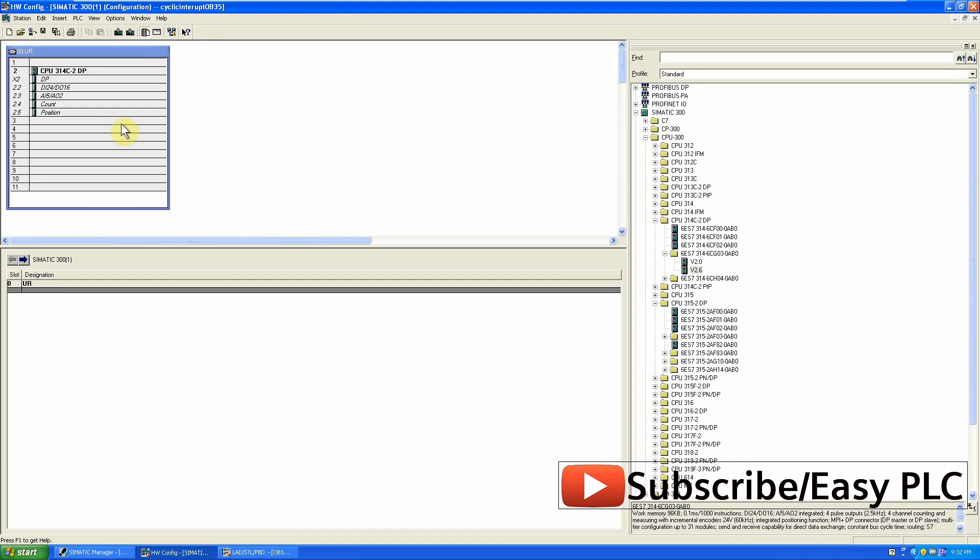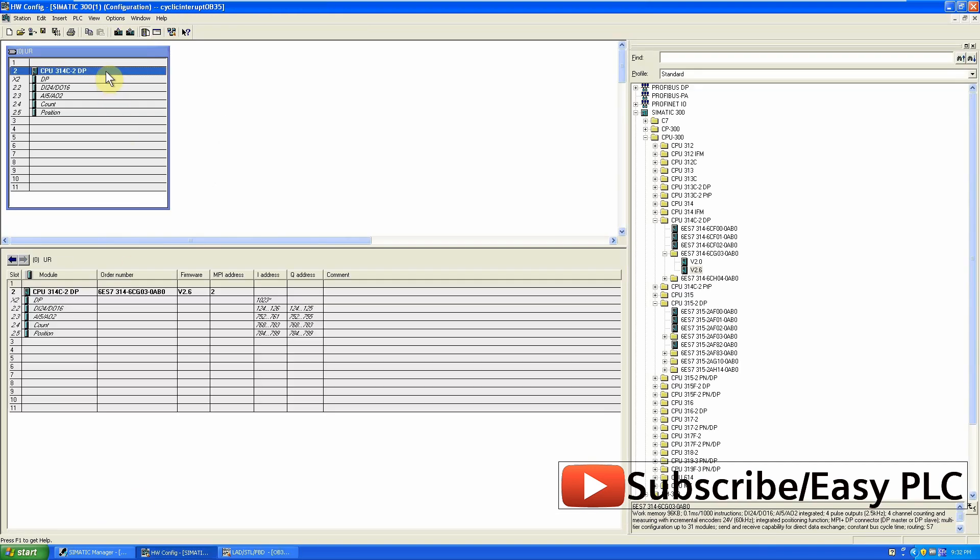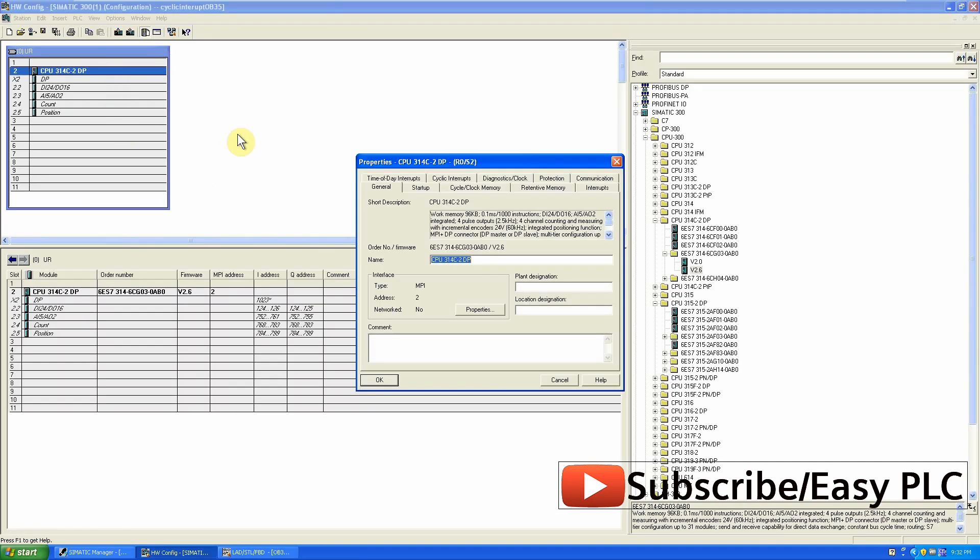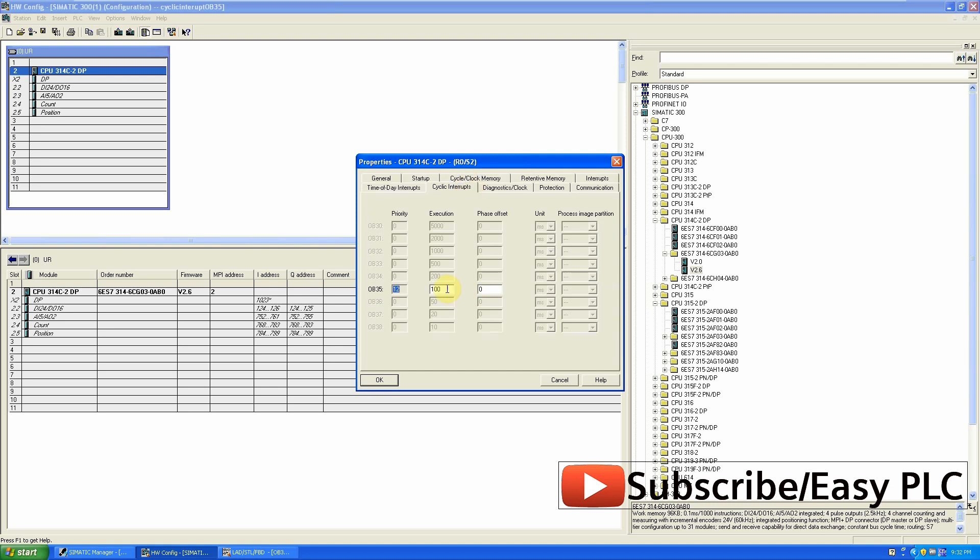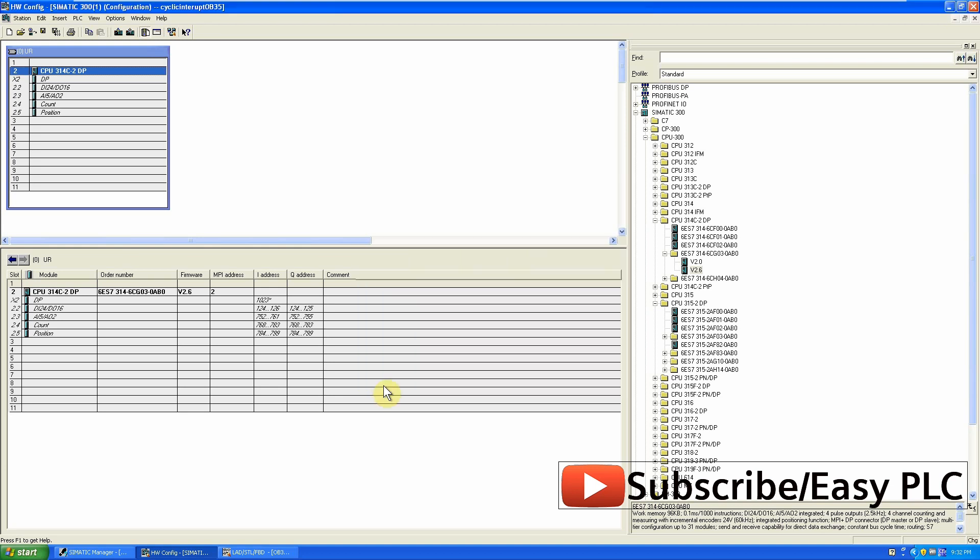We can change calling time of the OB35 from the hardware configuration of the CPU. To alter, just open the properties of the CPU and go to the cyclic interrupt menu. Here we can see OB35 is set to 100 ms. We will change it to 1000 ms which is equal to 1 second.